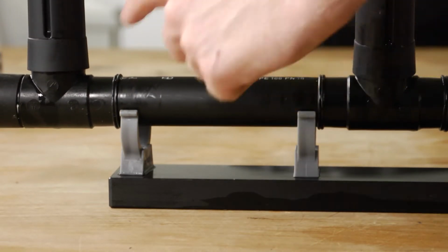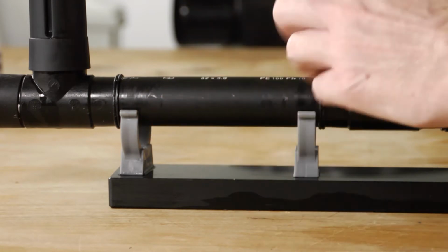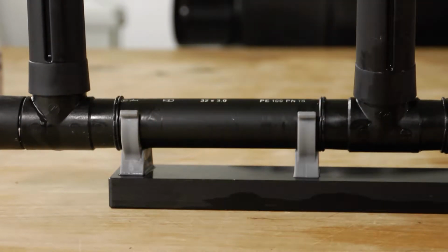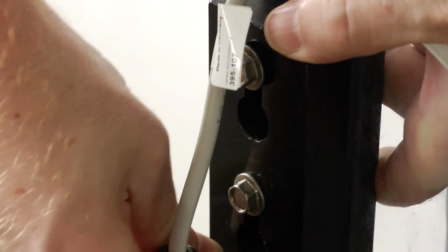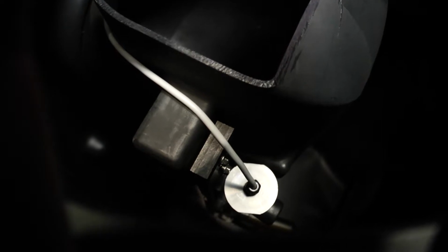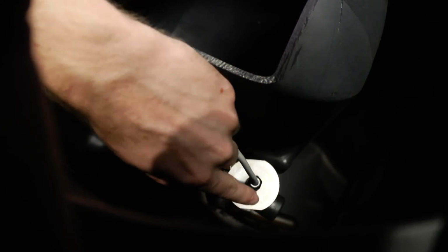First of all, make sure that the two lower retaining brackets are located between the sensors. The attachment points are on the outlet assembly at the side in the separator. Both screws should be tightened to 1 Nm to avoid floating. When the sensor is retrofitted, these holes must be drilled first.